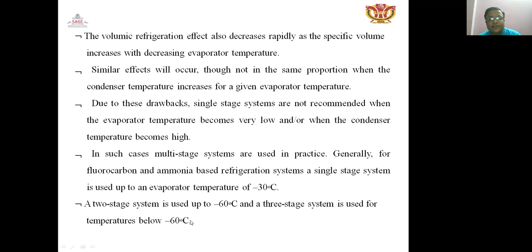A single stage system is used up to an evaporator temperature of minus 30 degrees centigrade. A two-stage system is used up to minus 60 degrees centigrade, and a three-stage system is used for below minus 60 degrees centigrade, up to around minus 100 to minus 120. These are the temperature limits for the three stages.